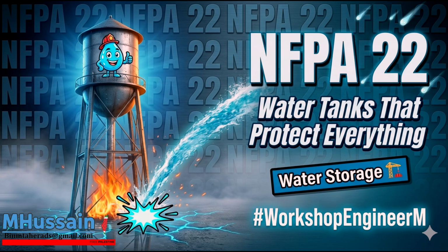And if we look at section 4.2.1.4, there's a very strict design parameter enforcing that control. The standard requires that your water supply must be capable of filling the minimum required fire protection volume in a maximum of 8 hours. That 8-hour rule fundamentally alters how you design the fill line. It's not just an arbitrary number, is it? Yeah, not at all. It means you have to mathematically prove that after a full-scale fire event or after a massive system drain from maintenance, the facility can be fully armed and ready to fight a second independent fire within a single standard working shift.